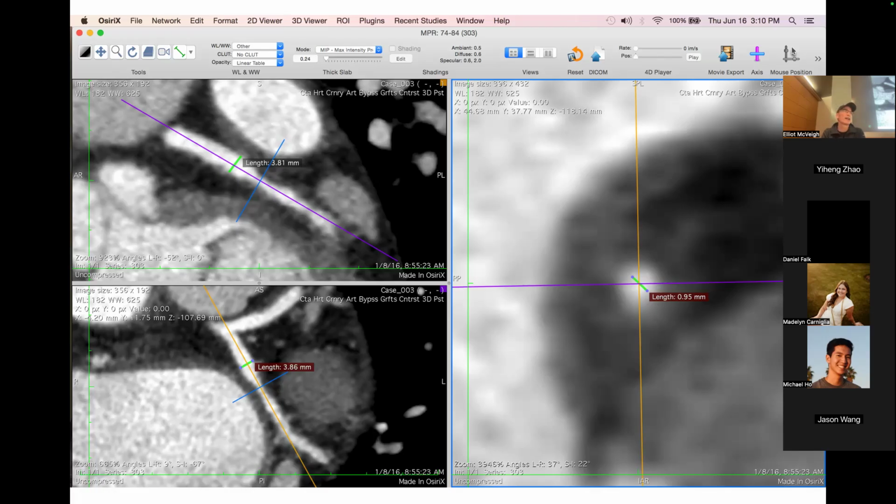Do you remember the point spread function of CT, right? When we characterize it with full width at half max, I've got a blob that has a full width at half max. So the point spread function of this imager is about 1.2 millimeters. As something gets smaller than that, the shape of that thing doesn't change, right? It still has that 1.2 millimeter full width at half max. As the object underneath gets smaller and becomes that little bead that we were talking about, it can get really tiny. It still will look like it's 1.2 millimeters in diameter. And so for this stuff, we're working right at the point spread function limit to quantify how big something is.